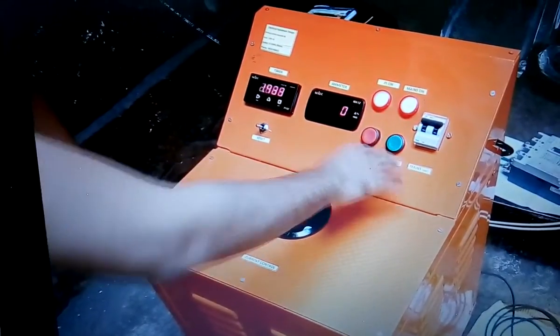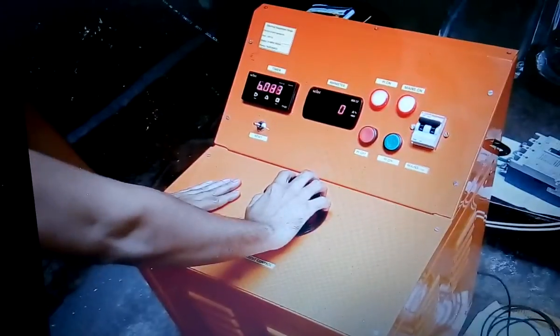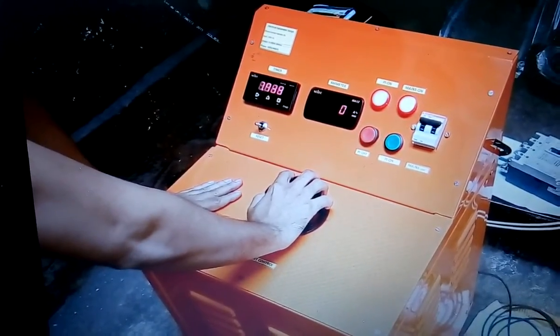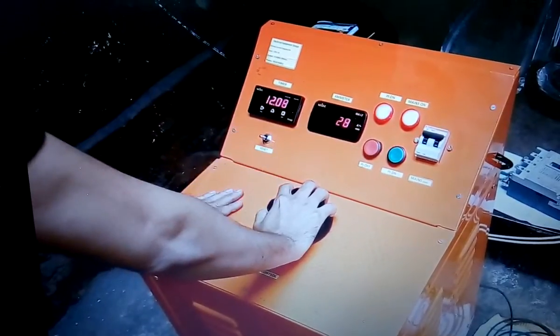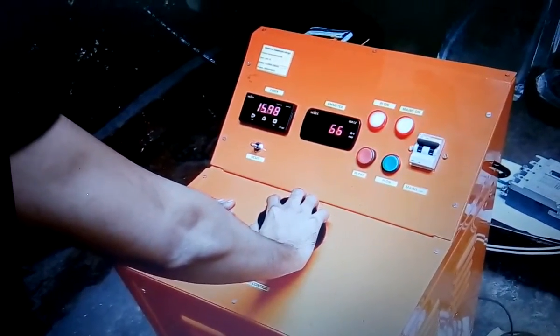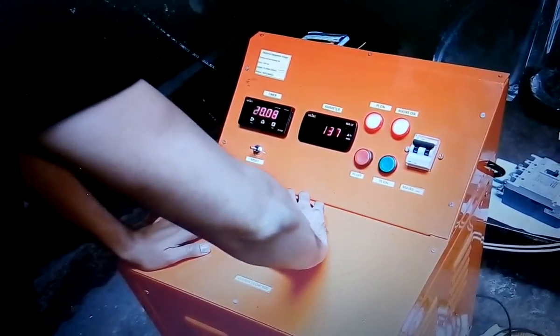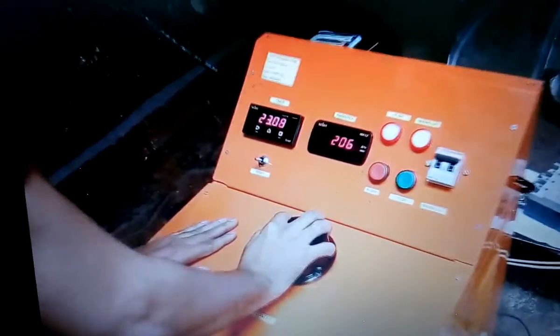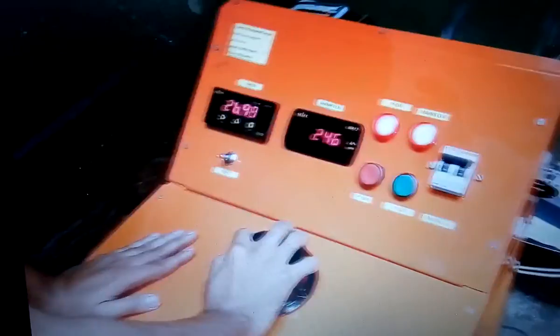So now the primary injection kit is ON. The time has already started and now we are varying the current and gradually increasing it to 350 ampere. It is now 32 ampere, 38 ampere, 59 ampere, 79, 89. Now it is increasing. You have to do it a little faster. I am doing it slow for demonstration purpose, but practically you have to do it faster.